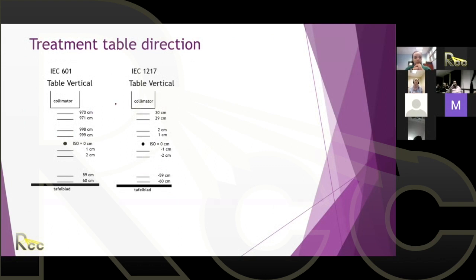But you have to know that some vendors would use 601. So, if you are looking at the table motion on the LINAC: if the table is going towards the LINAC, it will give you certain numbers. And if the table is going lower, away from the LINAC, it will start giving you 1, 2, 3, 4. So this is one system that could be used. Another system is that as you go towards the LINAC, you have plus - 1 cm above isocenter, 2 cm above isocenter. And if you go away from the LINAC, you have minus.